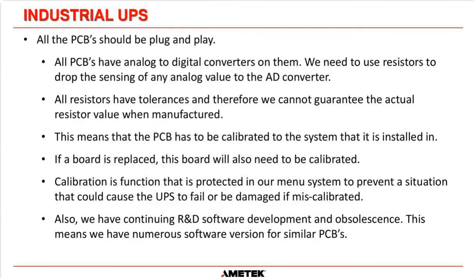So if the board is replaced, that board will need to be calibrated in most cases. And calibration is a function that is protected in our menu system on an AMETEK solid-state control UPS to prevent a situation that could cause the UPS to fail or be damaged if miscalibrated. We have to protect that menu system, because if we allow people to go in there and mess around with it, it's not clear in most circumstances what you're messing around with, and you could do something that could damage the UPS. So that is why it is password protected.